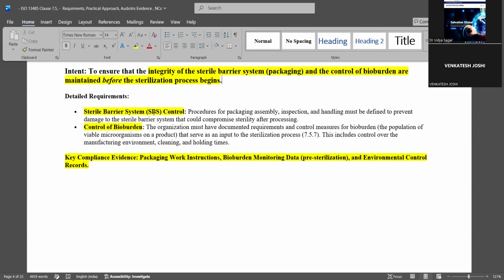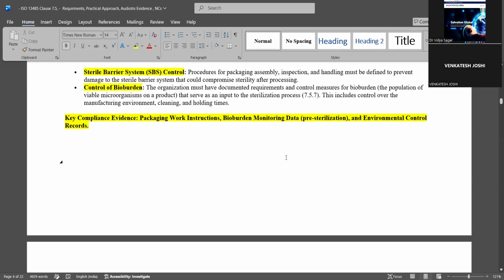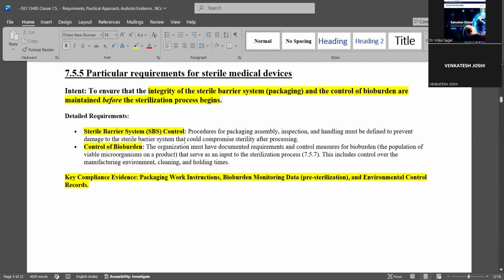So you should have total packing validation, control on the packing, control on the sterile barrier system, and control on the bioburden, whether you are maintaining it in the clean rooms or on the device, either by cleaning the device or cleaning the rooms with antiseptic, and periodic monitoring. That's why we give a packaging work instruction on how to open the package. You can't open a medical device package as you like. You can't just tear it as you like. There will be instructions for opening. That is the packaging opening work instruction, and bioburden monitoring data. As I told, every week or 15 days you need to monitor the bioburden, and environmental controls like humidity, temperature, and pressure. All this has to be monitored for sterile medical devices.